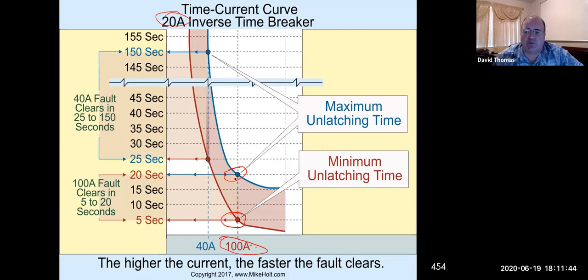But the idea with these inverse time breakers is that you give it enough time. So it's a delayed reaction, and it's going to trip. The delayed action of the inverse time breaker is sometimes wanted because the currents may be there for just split seconds and are not long term. Instantaneous breakers, on the other hand, would trip pretty quick at anything above 20 amps.